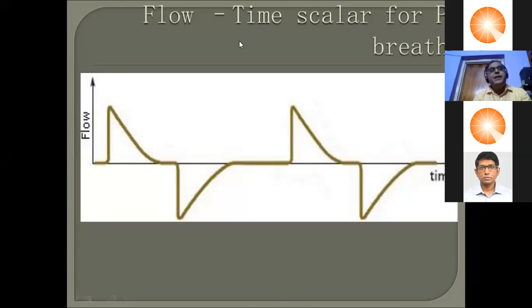What happens then? The pressure inside the lung is PIP. Pressure at the machine is PIP. So there is no gradient, and the flow stops. As you can see, the flow is a decelerating pattern. It continuously goes down until it reaches baseline. So there is absolutely no flow here. And then as my TI ends, my expiration starts.